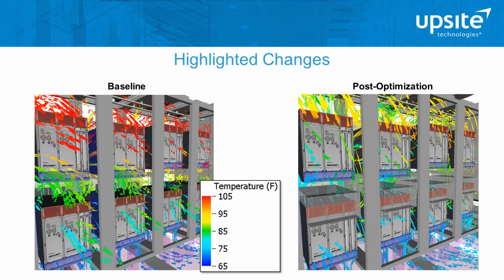There's no good trying to abide by the ASHRAE rule of measuring at two-thirds the height of the cabinet, 40 centimeters out. That's really not going to do the trick. What matters is what actually enters the individual inlet of each piece of IT kit, whether that inlet is on the side or the front, it doesn't matter. This particular picture is another highlight of the changes we made at City.